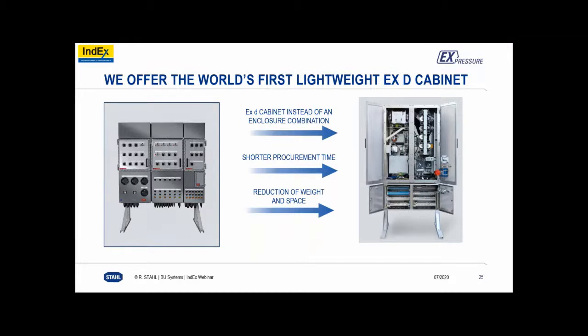It's not easy to tell, because as I said, ExPressure is a premium solution. So if you compare the prices of the cabinet to the conventional Ex d solution, it costs more alone because of the material of the enclosure and the size of the enclosure. But you have only one cabinet, only one enclosure, less weight, and you reduce your commissioning, setup and maintenance time in the product life cycle.